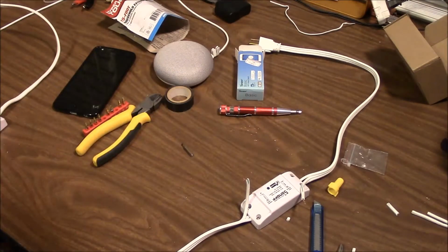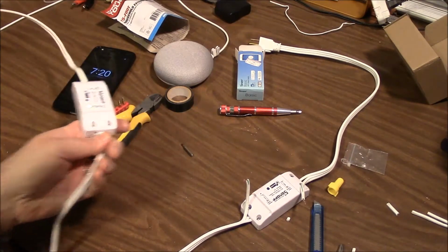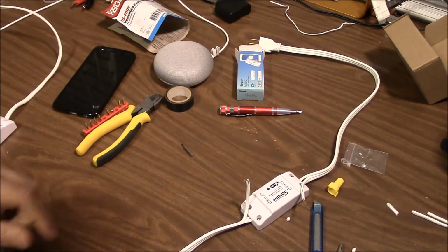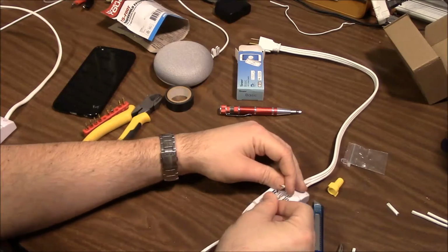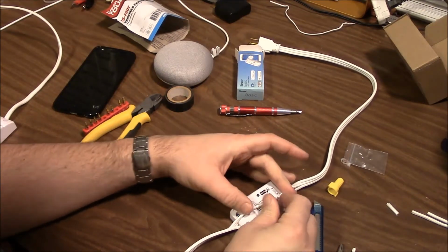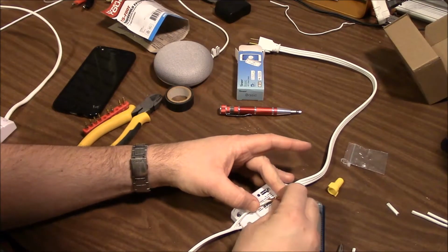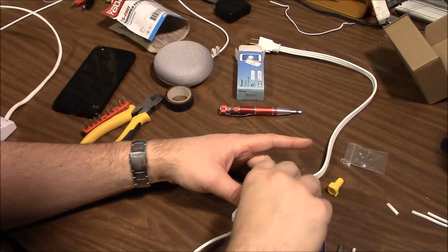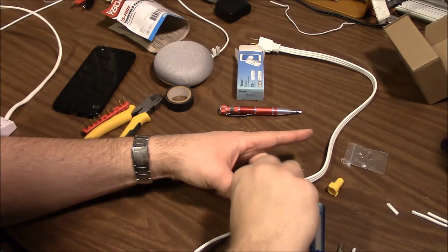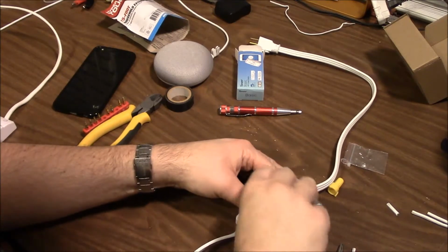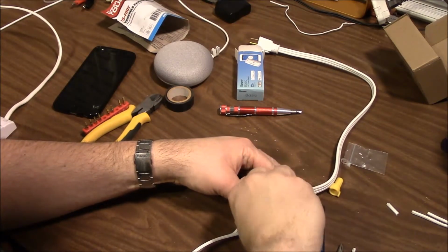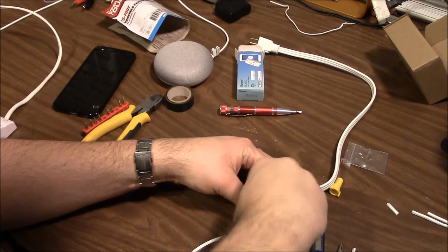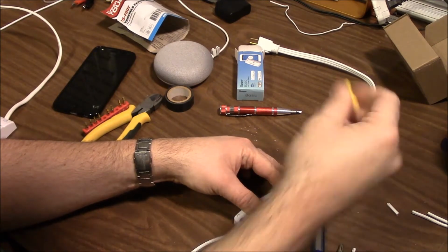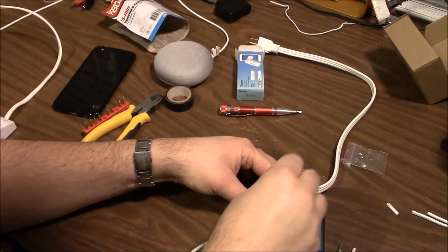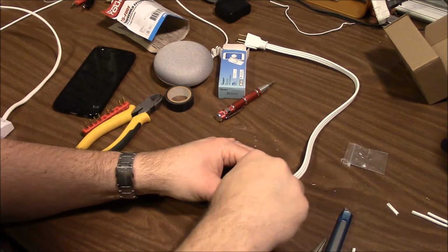All right, so if we were just doing a two-wire like we did over here, we'd pretty much be done. But since we've got the third wire here, the ground wire, we gotta take that into account. So what we're gonna do is we're gonna twist the wire like that. Get the wire nut on there.